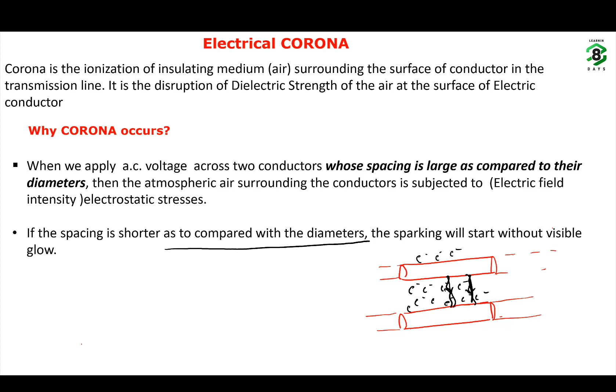The phenomenon of hissing noise, violet glow and production of ozone gas in an overhead transmission line conductor is known as the corona effect. So when corona occurs, the conductor makes a hissing noise and there is a violet glow surrounding the surface of the conductor, and ozone gas is produced from the transmission conductor. Even after occurrence of corona, if you further increase the transmission voltage or the electric field intensity at the surface of the conductor, then this corona effect will become more and more pronounced, which is identified by more hissing noise and more violet glow. Understand? And there is always a chance that even after occurrence of corona, flashover can occur between the two transmission conductors. The flashover or the short circuit can occur between the two transmission conductors.